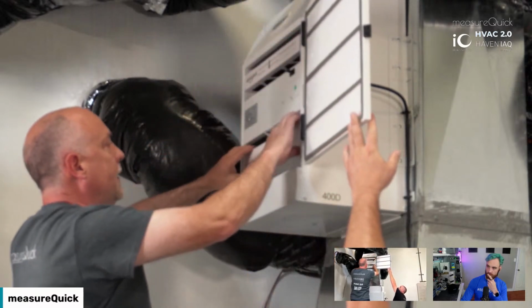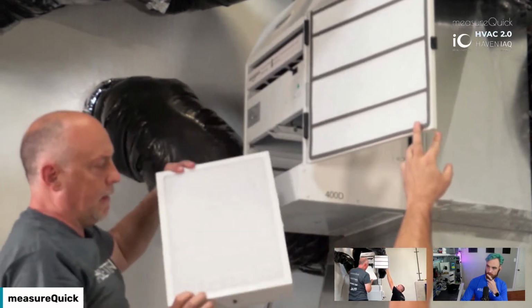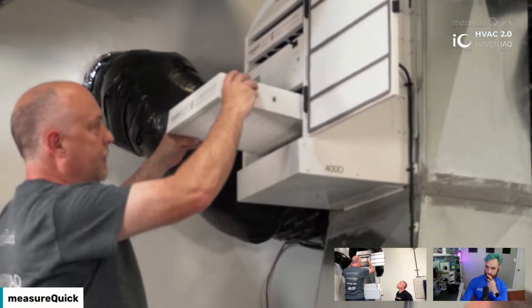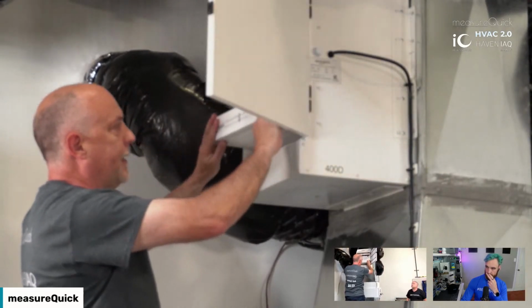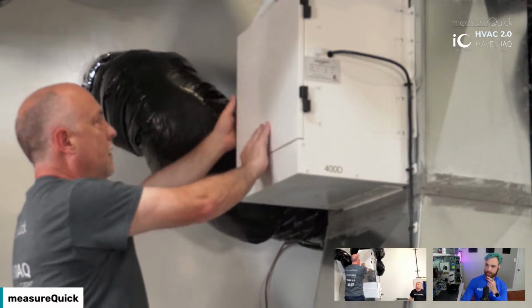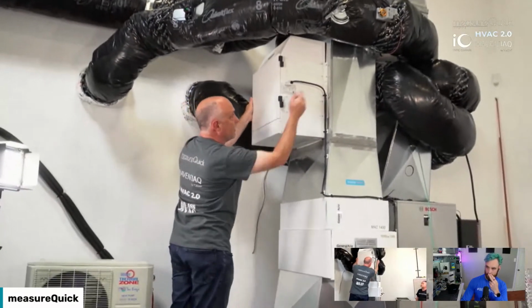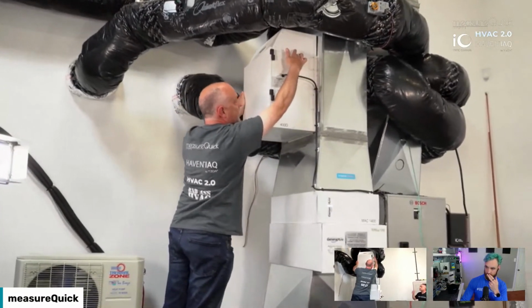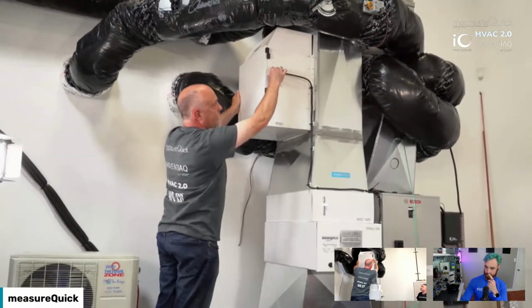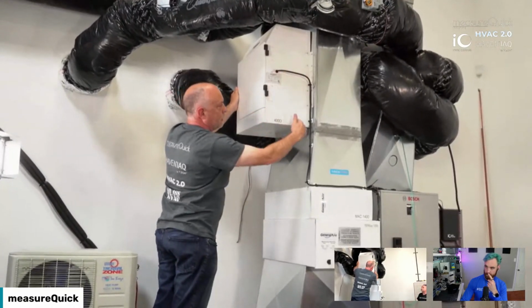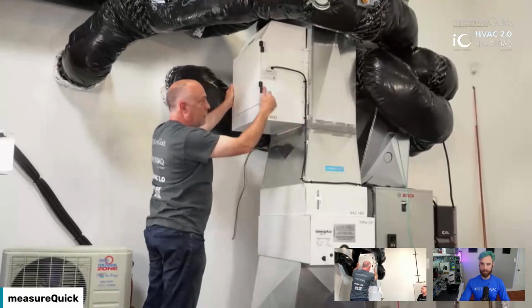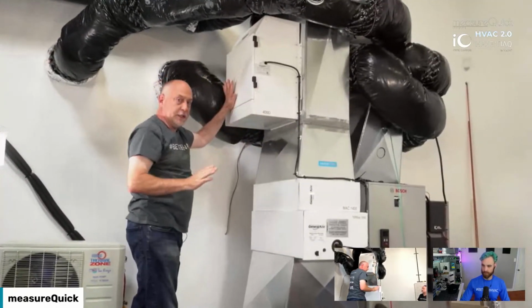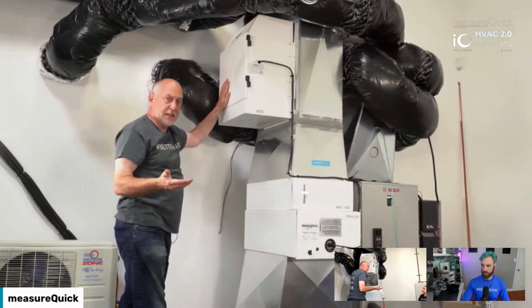And then down below here is actually a HEPA filter. This is a bypass, and what it's doing is taking a small amount of the air that's coming in the duct. It just goes in the top. There's a fan that drives this through, on a rheostat, and then it exhausts it back into the return air duct. So this is removing all the really small particles and also some odors through the charcoal.